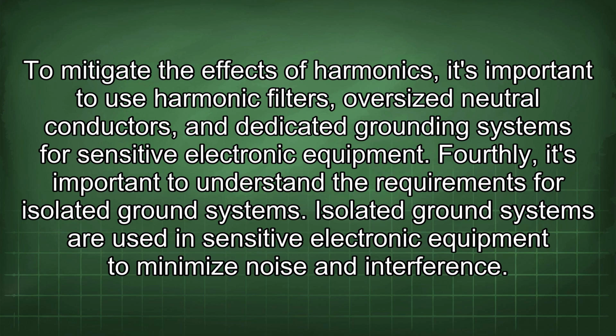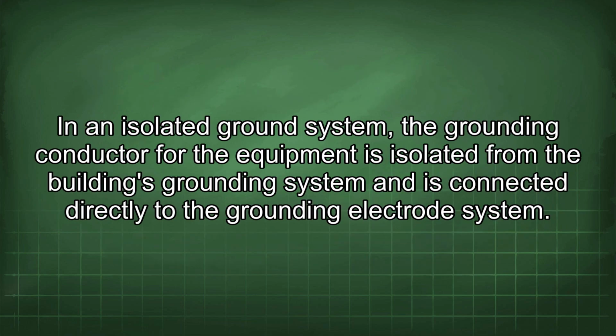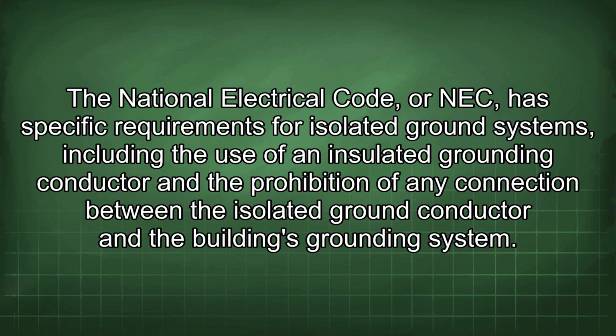sensitive electronic equipment. Fourthly, it's important to understand the requirements for isolated ground systems. Isolated ground systems are used in sensitive electronic equipment to minimize noise and interference. In an isolated ground system, the grounding conductor for the equipment is isolated from the building's grounding system and is connected directly to the grounding electrode system. The National Electrical Code, or NEC, has specific requirements for isolated ground systems, including the use of an insulated grounding conductor and the prohibition of any connection between the isolated ground conductor and the building's grounding system.